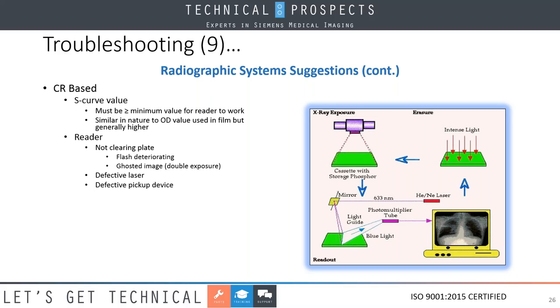The flash is deteriorating. You're getting a ghosted or double exposure. You may have a defective laser where it's not exciting in order for the phototube to read, or maybe even the photomultiplier tube is defective. All right, computer, are we getting the information from the photomultiplier tube over? Is that link complete? And also we've got calibrations of the monitor, or maybe we have a bad display.